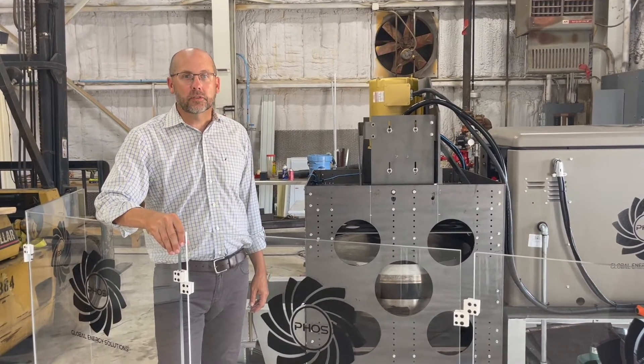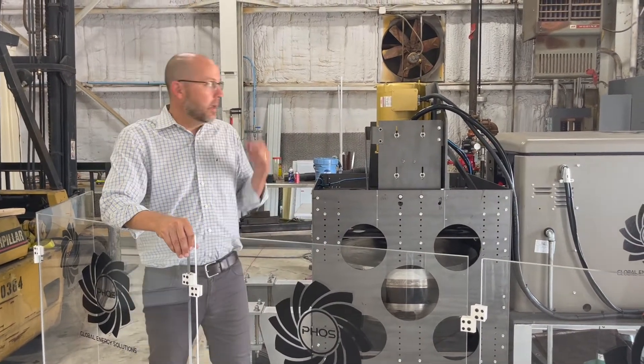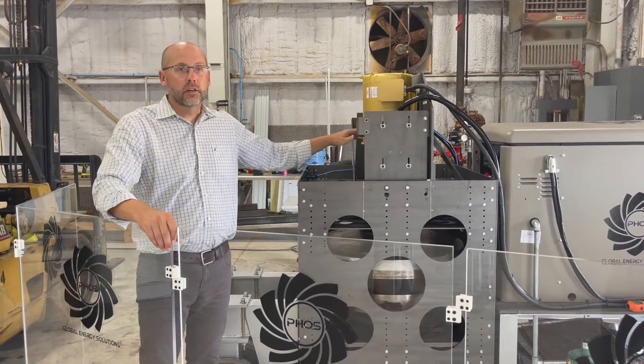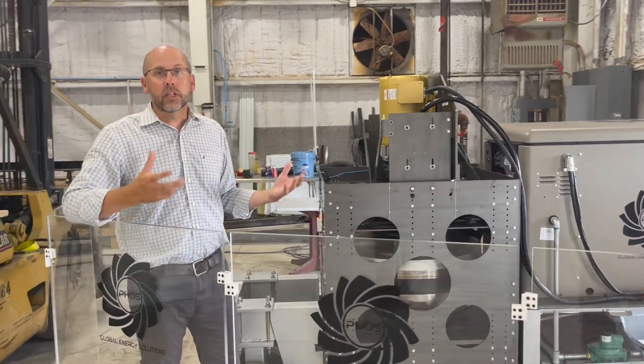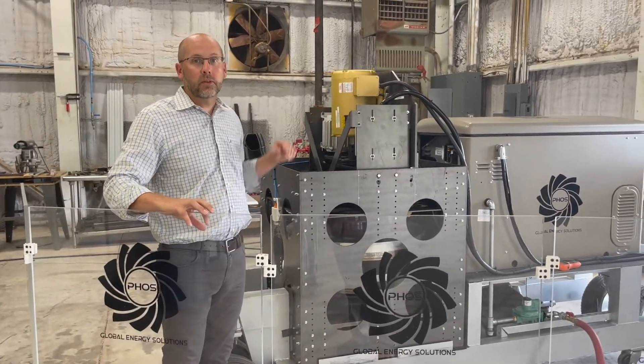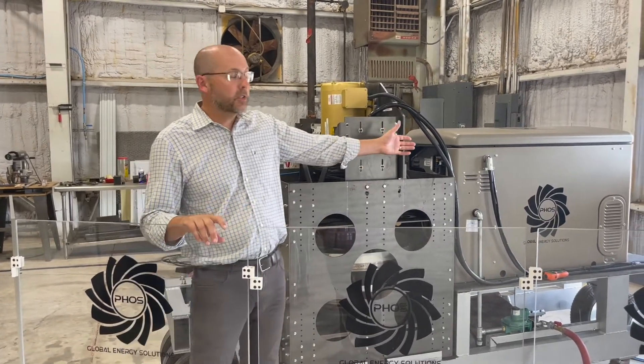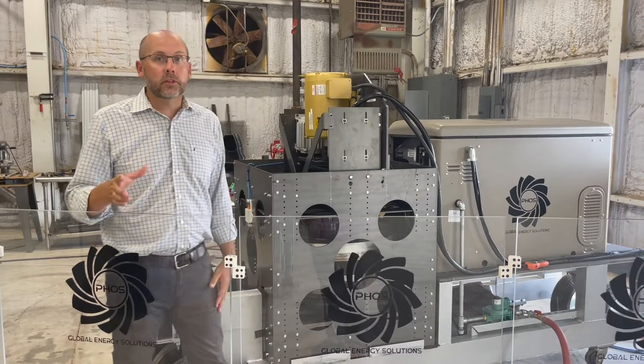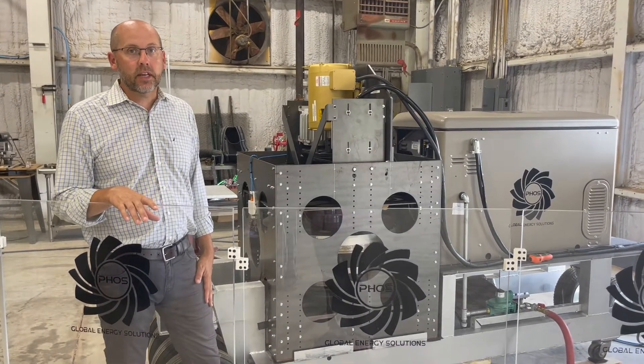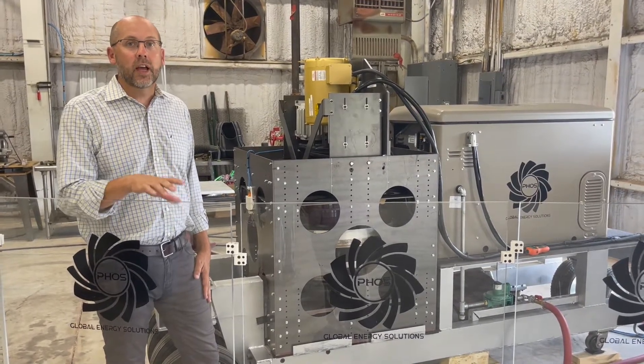So what is an advanced flywheel energy storage system? Well, as the name suggests, a flywheel that is driven by a motor incorporates an electrical generator and is really agnostic as to what provides energy to the motor. This motor may be driven by a grid if energy is cheap, by a backup generator such as the one here, or by renewables such as solar panels. It's really agnostic as to the source of the energy and allows you to control your energy production and usage.